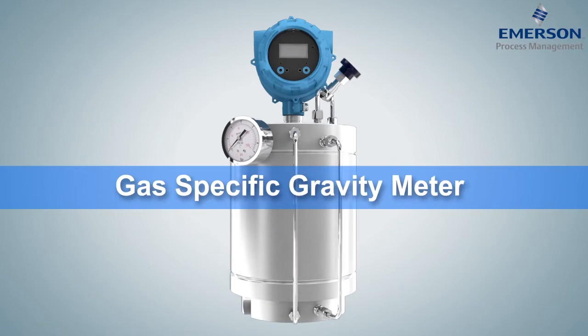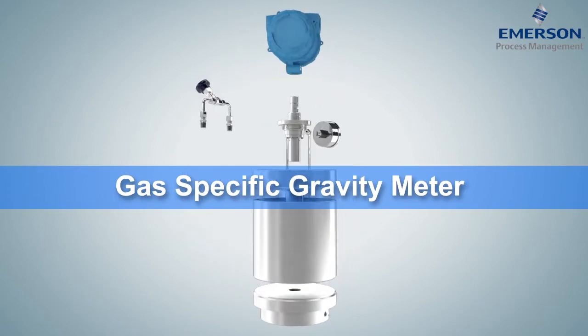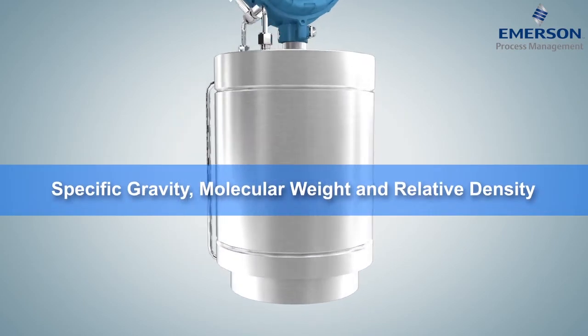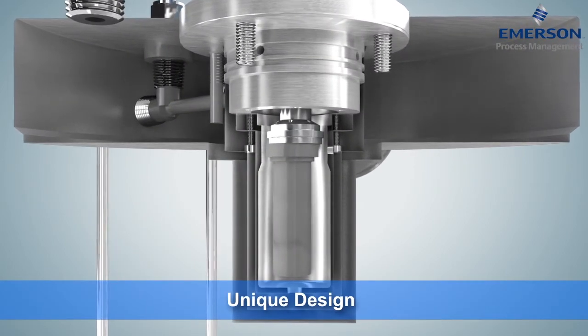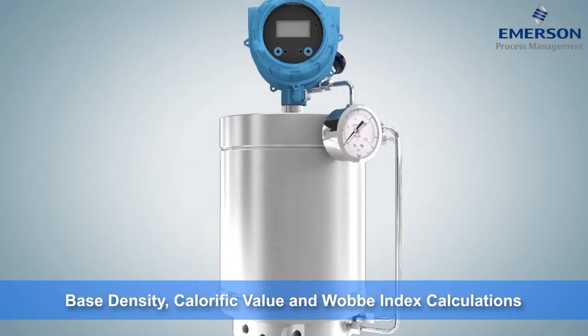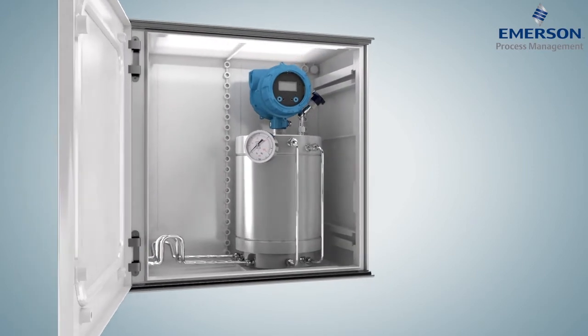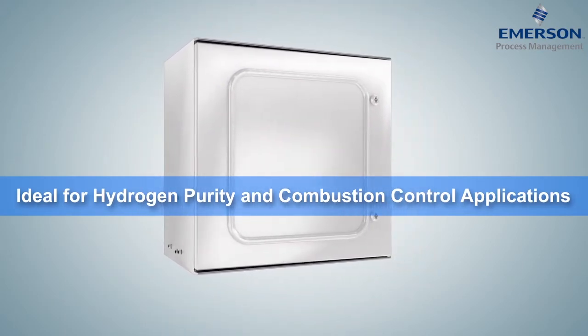Using the same vibrating cylinder technology as the GDM, Micro Motion's Gas-Specific Gravity Meter, or SGM, directly measures specific gravity, molecular weight, and relative density. The SGM's unique design eliminates the need for external temperature, pressure, and compressibility measurements, offering enhanced calculations of base density, calorific value, and Wobbe Index. The SGM is an ideal fit for applications like hydrogen purity and combustion control.